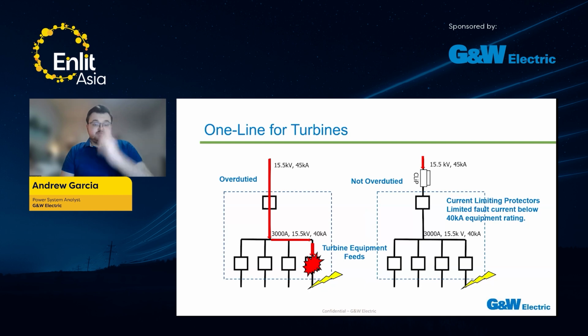So here's a representation of how exactly this looked. You have the overduty condition without the CLIP, risking the system downstream being overdutied, and therefore a system fault could cause the equipment to explode and harm any nearby personnel or other equipment. They install a CLIP. That CLIP limits the fault current downstream to a rating that's less than the equipment can handle. And now your system is good to go and it's properly protected.